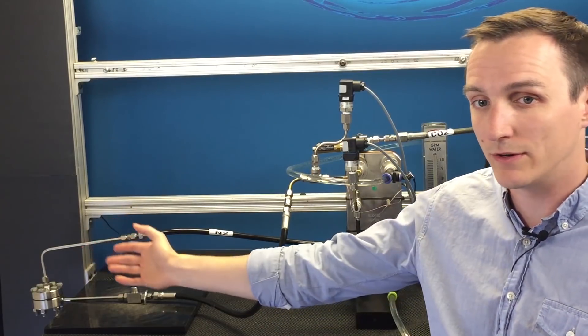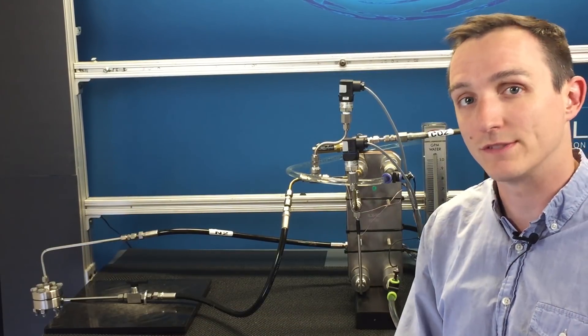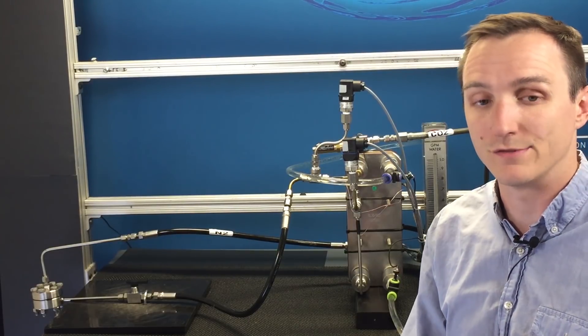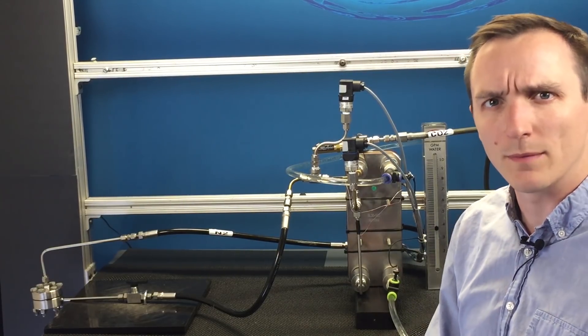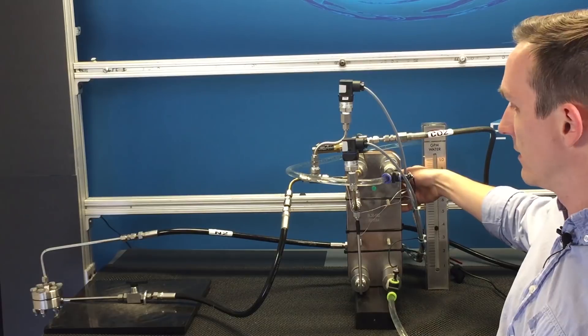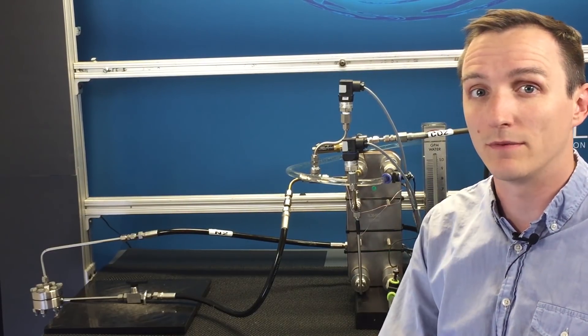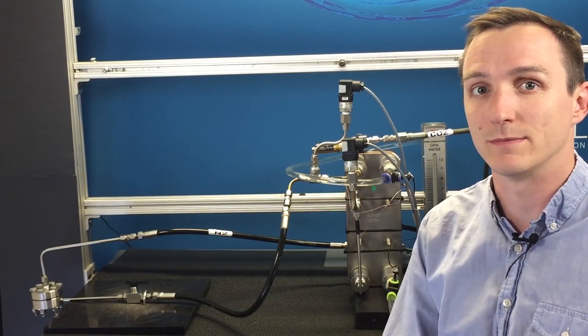Here we have the Equilibar dome loaded back pressure regulator which will control the saturation pressure of the CO2 in the evaporator providing isothermality. The Equilibar is controlled by a QV pilot regulator which is in the back and will control the supply of nitrogen to the dome of the Equilibar. Let's go run the system and see what happens.